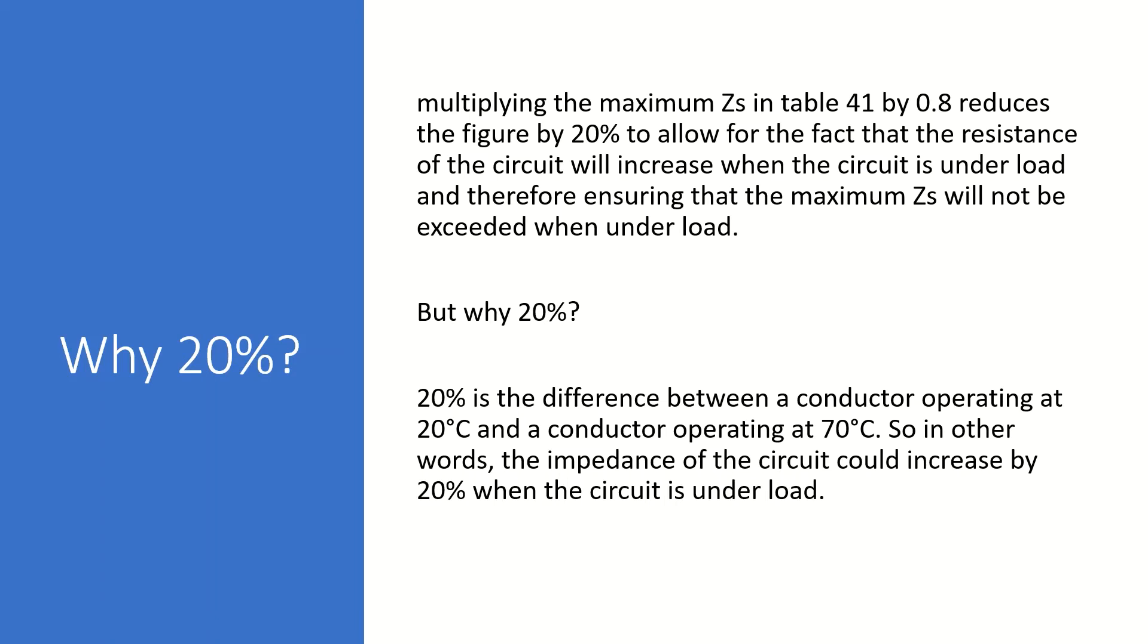But why 20%? Well, 20% is the difference between a conductor operating at 20 degrees C and a conductor operating at 70 degrees C. So in other words, the impedance of the circuit could increase by as much as 20% when the circuit is under load.